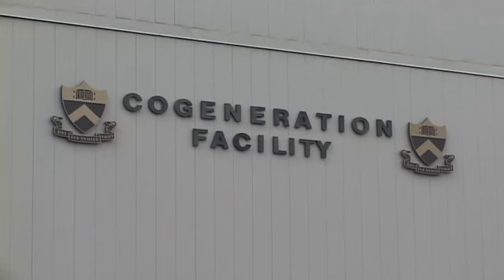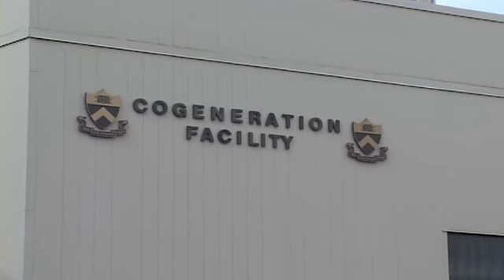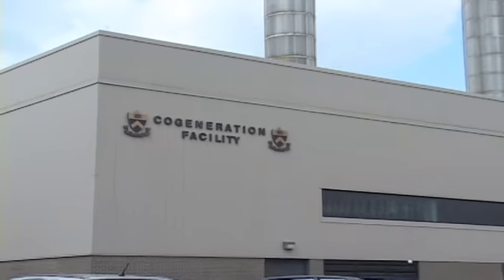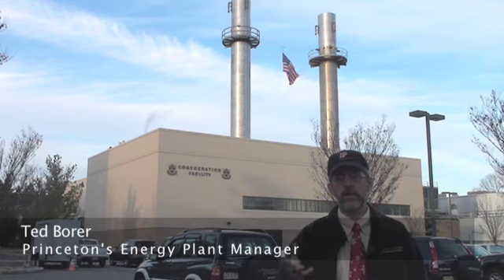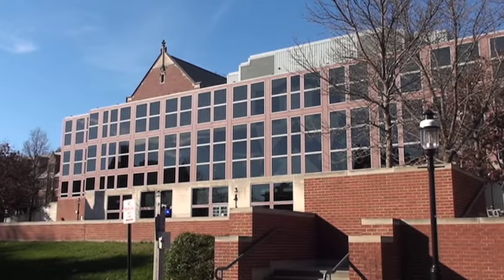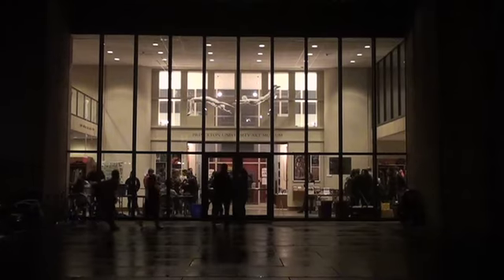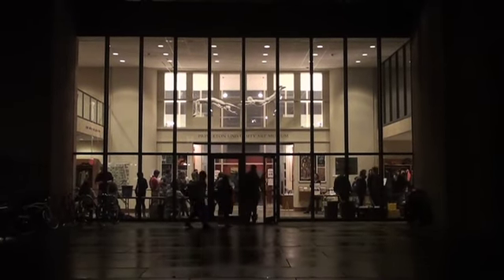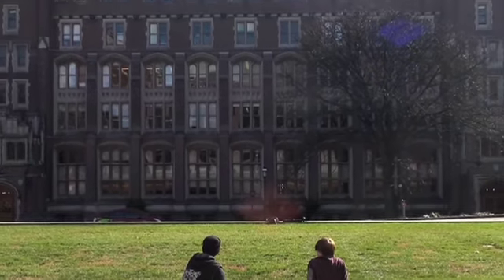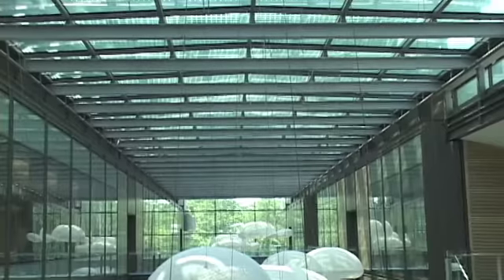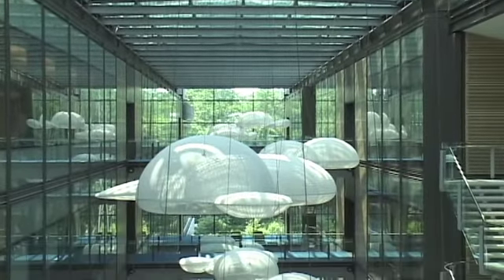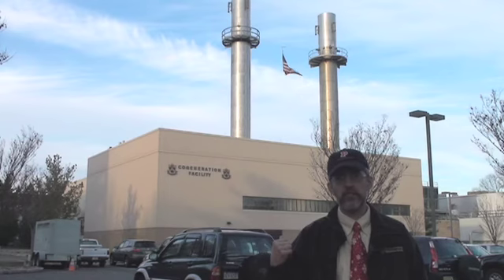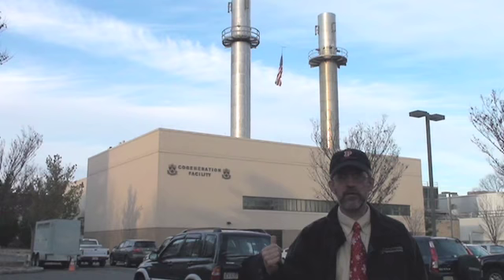The cogeneration plant is really the heart of our district energy system. An important thing to understand is that if we have 150 buildings we're serving, and maybe 12,000 people on our campus as the daytime population, normally without the cogeneration plant we'd need 150 boilers and 150 air conditioning systems. With a central energy plant and district energy, I'm able to have 3 boilers and 8 chillers instead of 1 in each building.